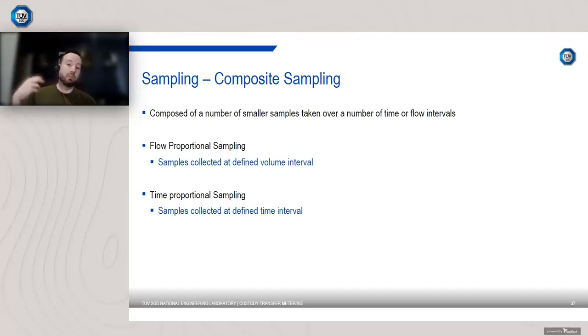There are different techniques. You can use time proportional, where you collect samples at a defined time interval. Flow proportional is more common, and this is where the samples are taken at a rate which is proportional to the rate of the flow of your liquid in the pipeline. So you've usually got some kind of flow meter or flow measurement device that is setting the pace of the sampling system.